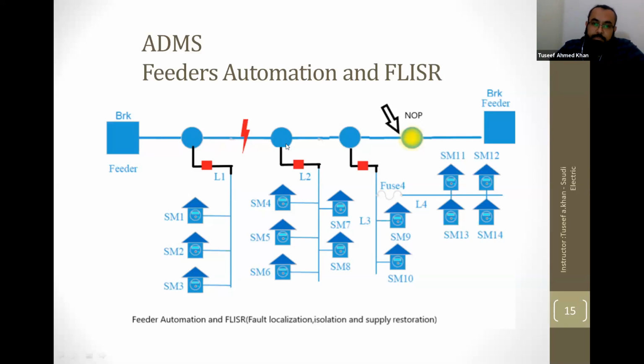The next step, the ADMS software will switch on this NOP and your supply will be restored. The system will check the loading here and there, and give you a picture of how effective your fault localization, isolation, and supply restoration is, and if there is some loading condition, you can easily know.